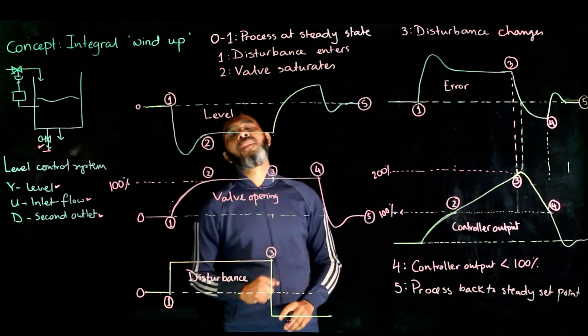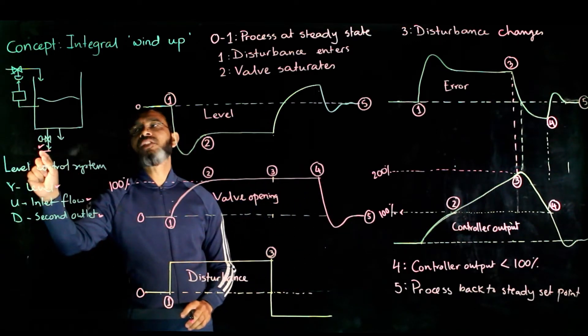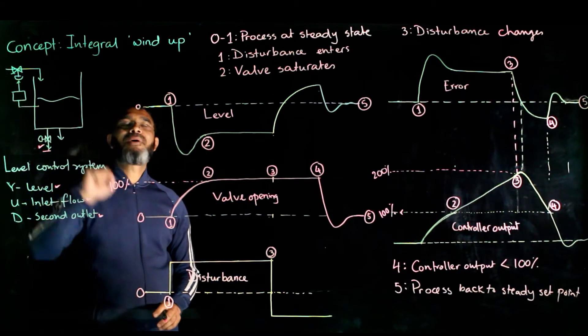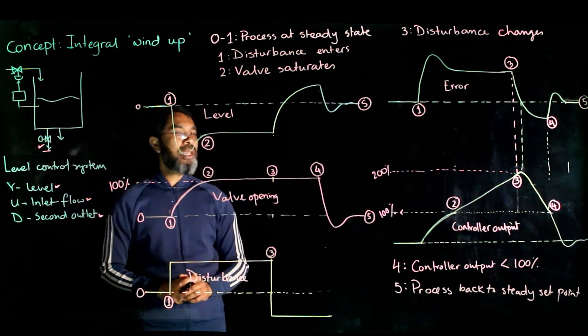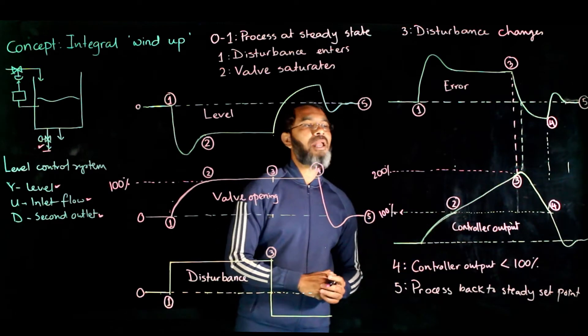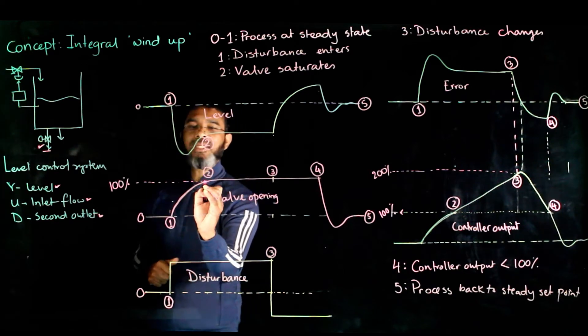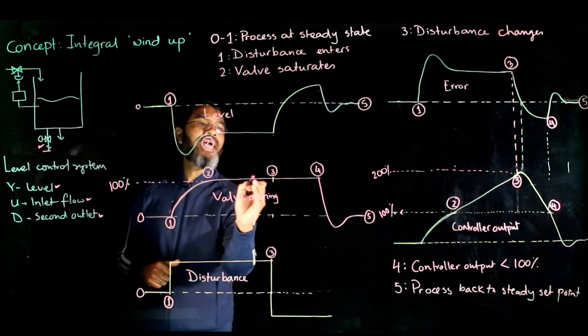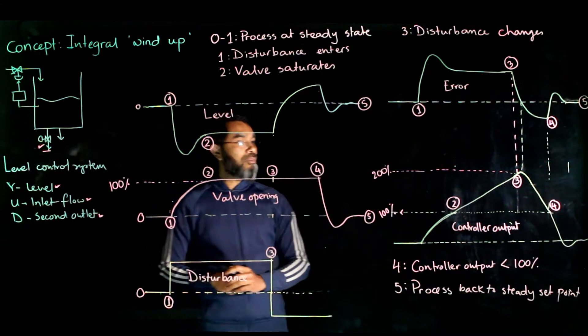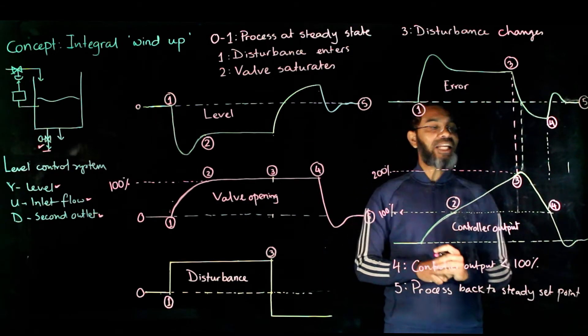In this scenario, the disturbance has a magnitude such that even at 100% valve opening, the level cannot be maintained at the desired value. The controller calculates a valve opening beyond 100%, but when it reaches 100% the valve saturates and cannot move further — it remains at 100%. However, due to persistent error, the integral action keeps accumulating.